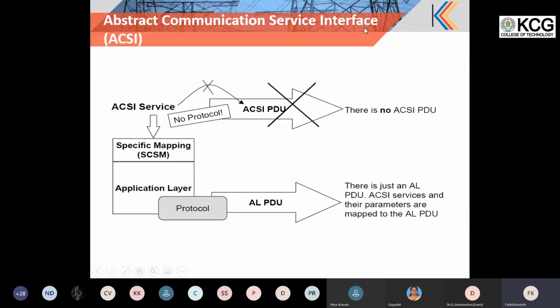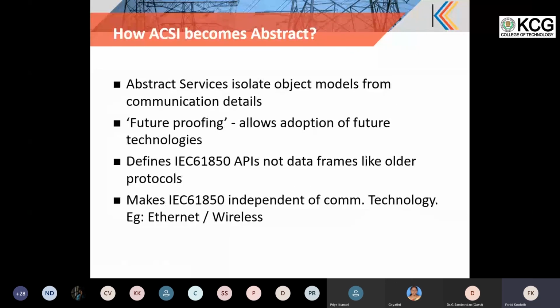It is not mentioning any protocol, but how the data can be exchanged is defined in the abstract communication service interface. And the actual payload or protocol mapping is defined by the specific communication service mapping, from ACSI to the specific communication service mapping, like GOOSE, MMS, everything is defined there. That is why 61850 is named a future-proof protocol, because the actual payload is hidden from it. I have already mentioned this future proofing. It is like an API, application programmable interface, the abstract communication services.